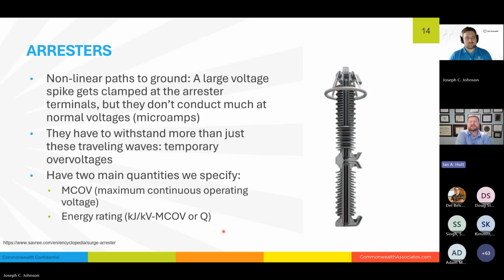What we're seeing on the slide here is a standard station class arrester with the corona halo on it. Essentially, it's kind of like a transistor in a way. When we have nominal voltages, the things we expect and that this device is rated for, there is a small amount of current, microamps, going through this device. It's essentially allowing the system to do its thing. But the minute we see voltage spikes in its operate range, this thing goes from conducting a small amount of current to being a pretty low impedance path to ground. By doing that, it clamps that voltage down, and it can do this very, very quickly. So when these transients come, voltage spikes, lightning strikes, and switching surge events, these devices can operate, clamp voltage and help protect our equipment in the vicinity.